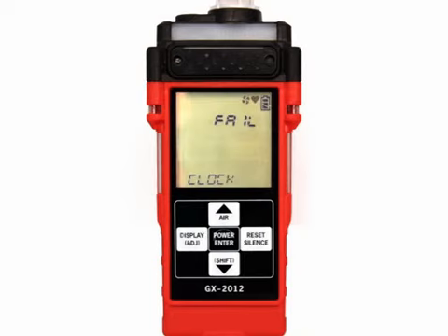If a clock failure alarm occurs, the internal unit date has been changed to something unreasonable, like month 15 or day 34. Press and release the Reset Silence button to continue into normal operation. There will be no data logging function if you operate the instrument after a clock failure. Attempt to change the date using the Date menu in maintenance mode. If the date cannot be set correctly, contact RKI Instruments as soon as possible.